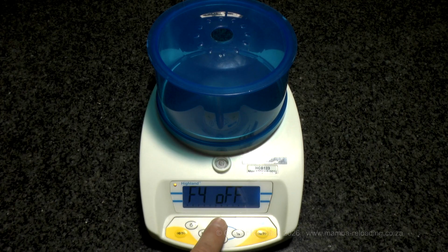Press Mode to advance to F5, IEC, then press the yellow Zero Tare button to enter. This function controls the calibration method. Press Mode to toggle between INT, internal, and E, external calibration. I select external calibration, E, and save it by pressing the yellow Zero Tare button.